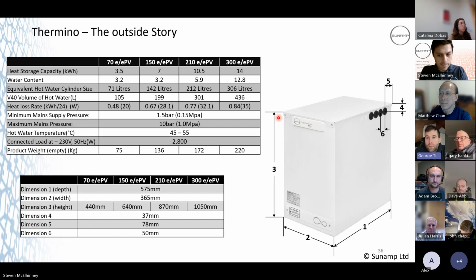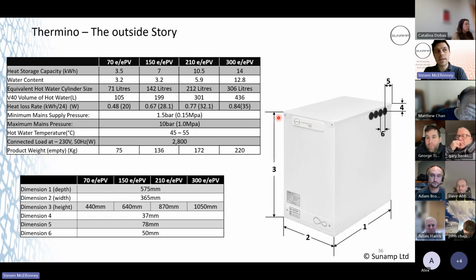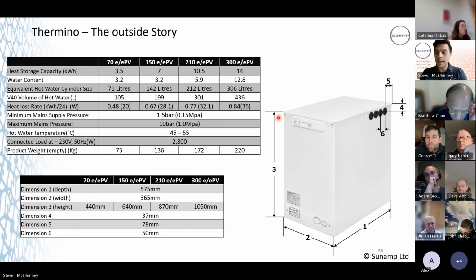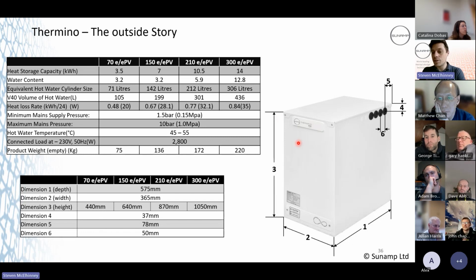Secondary returns on these. So circulated hot water, you wouldn't recommend that? You can do them, as long as the customer understands that their energy costs will be a bit higher with that one, George. Like with any secondary return, what I have seen some customers do is put their secondary return on in the morning. They isolate the pump, and when they get up in the morning they put the switch on. That activates the pump, gets the secondary return up to temperature, and then they use their hot water. When they're finished, they just turn it off again. Or the pump's controlled by a timer, just to stop it running constantly, and your energy usage.